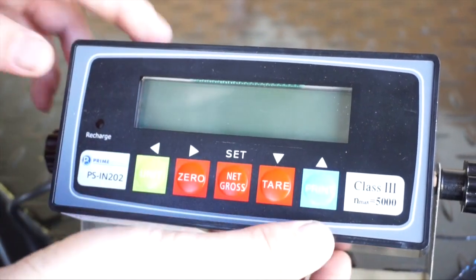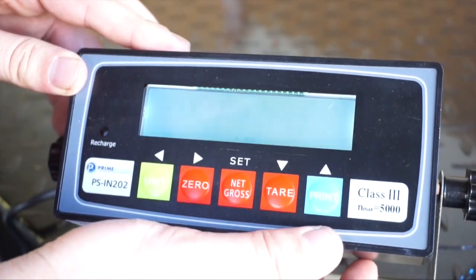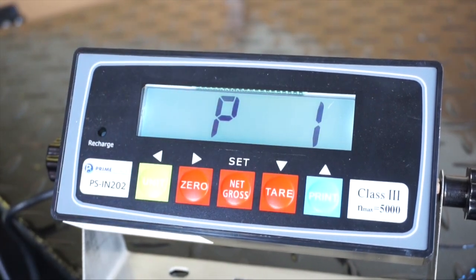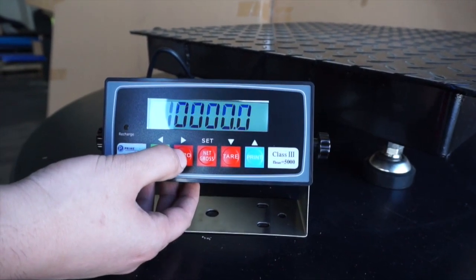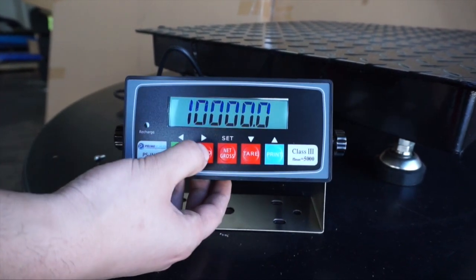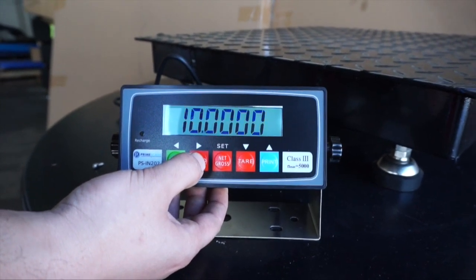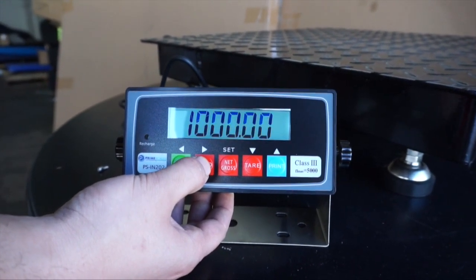Turn on the indicator and you should arrive to P1. Press zero to enter parameter 1. Here you can set capacity of scale up to 10,000 pounds. The zero button with the right arrow above moves the decimal points in the capacity. The print and tare button moves the calibration capacity up or down.